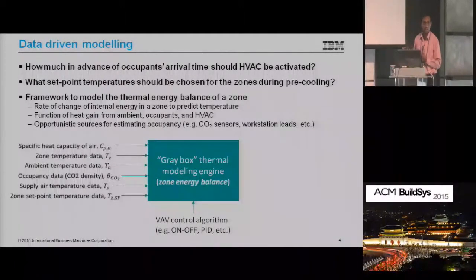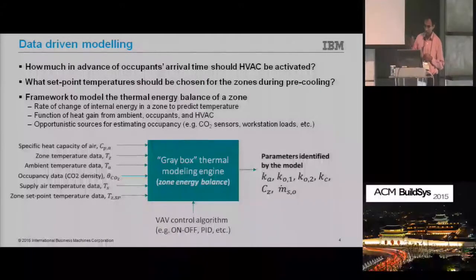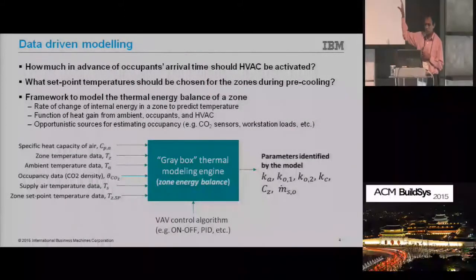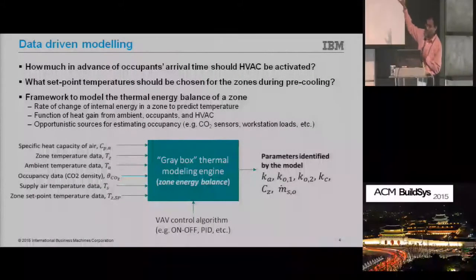If we have that mass flow rate data, that's well and good. But if we don't, we can use the VAV control algorithm to indirectly estimate it, which is what we do here. Then, performing a simple regression analysis, the model identifies a bunch of parameters. The details are in the paper, so I won't go into them, but essentially we minimize the error between the zone temperature predicted by the model and the zone temperature actually recorded by the internal temperature sensors in the building.